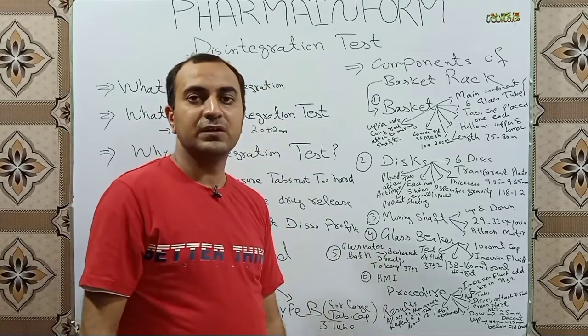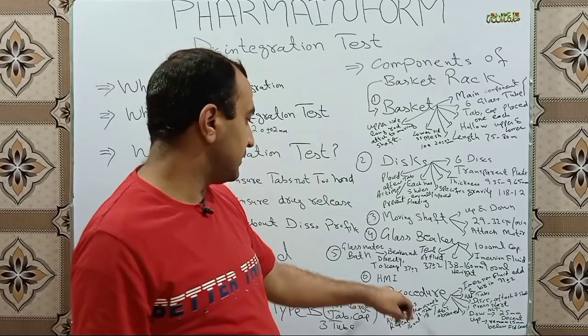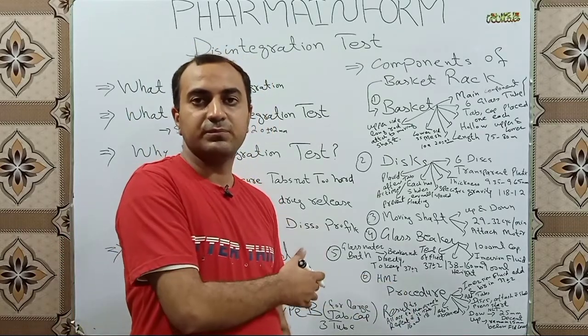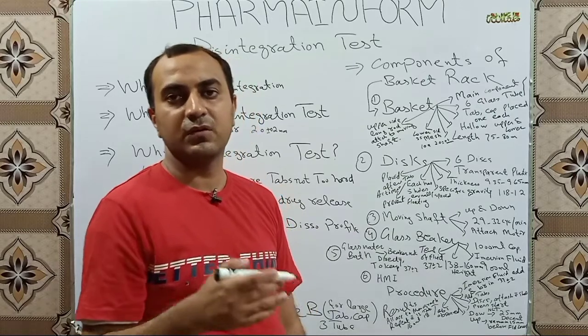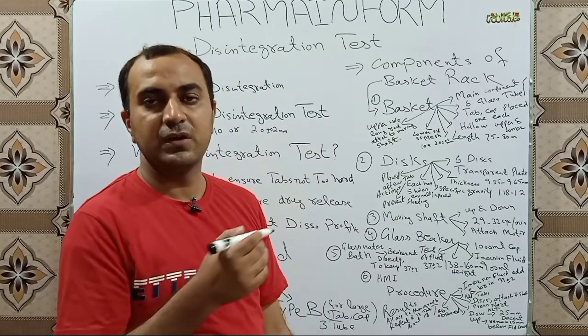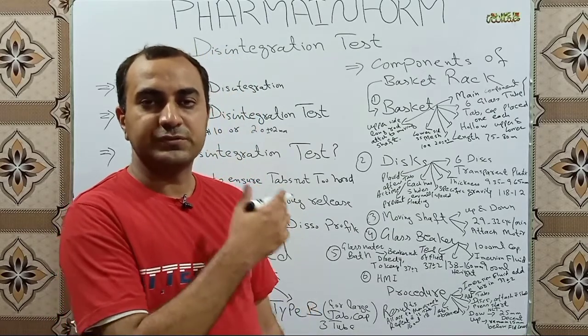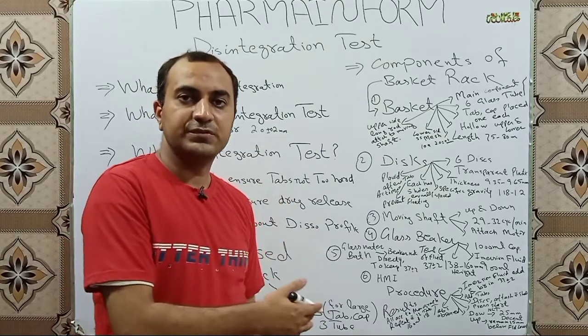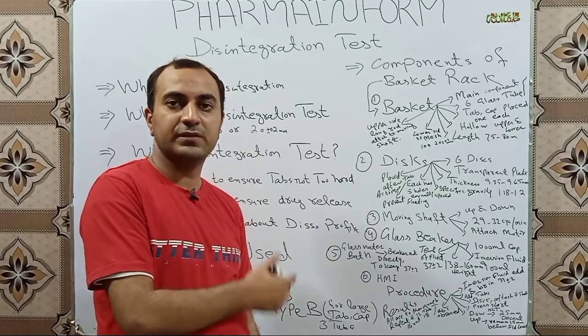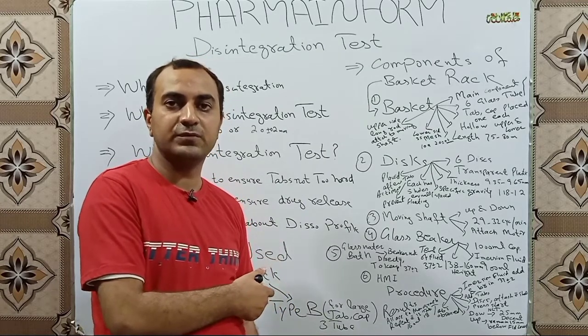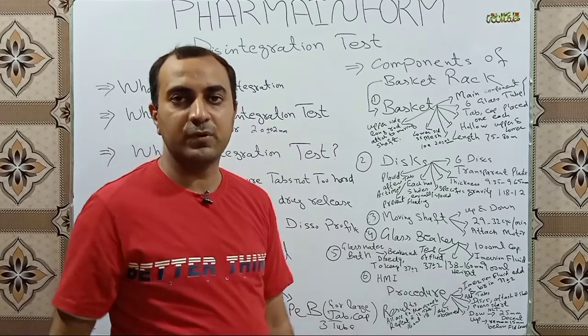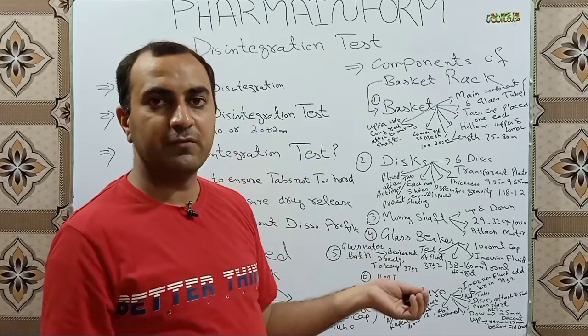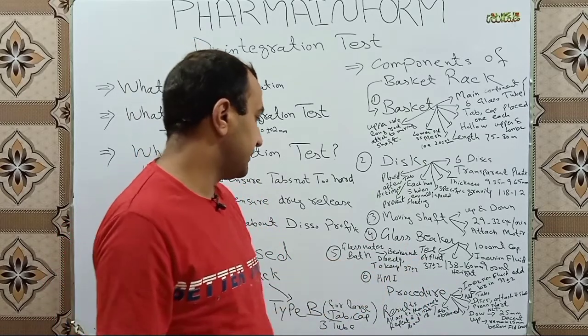The HMI — Human Machine Interface — has a touch screen or different buttons used to start and stop the process, adjust the temperature, and it also has a timer or stopwatch that gives us the disintegration time, telling us how much time our tablets took to disintegrate.